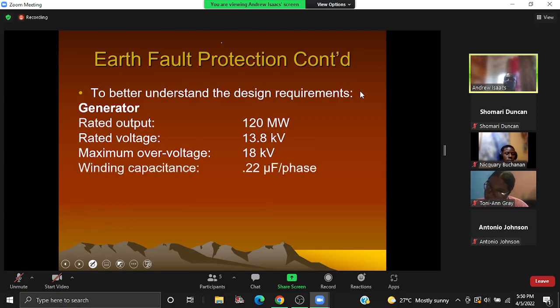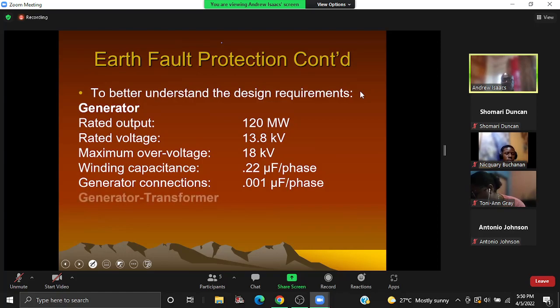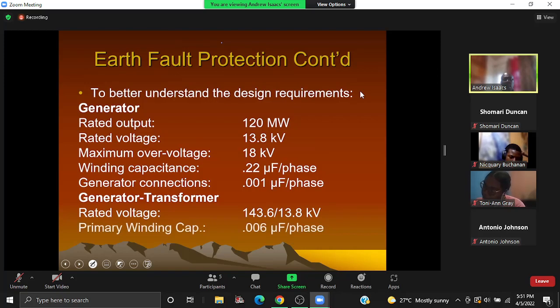The winding capacitance is 0.22 microfarad per phase. For the generator connections, we have 1 nanofarad per phase. And for the generator transformer, the rated voltage 13.8 kV, and the winding capacitance 0.006 microfarad. So we have capacitance as a result of the windings for the generator. We have capacitance for the connections, and we have that connecting to the transformer.